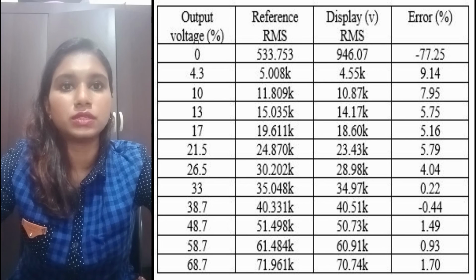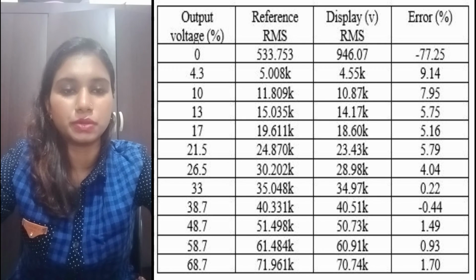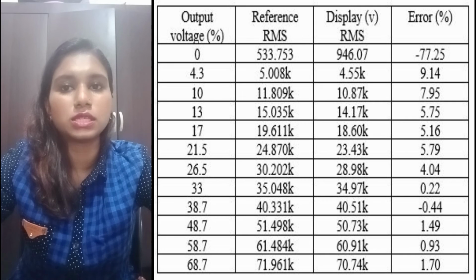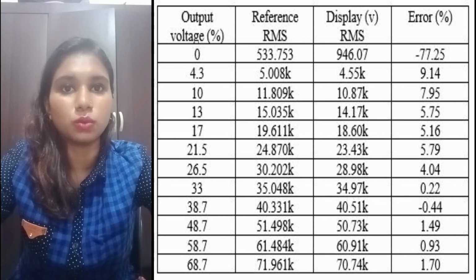Okay, when the output voltage is 58.7%, the reference RMS is 61.484 kV. The display value is 60.91 kV while the percentage error is 0.93%. When the output voltage is 68.7, the reference RMS becomes 71.961 kV and the display value is 70.74 kV while the percentage error is 1.70%.